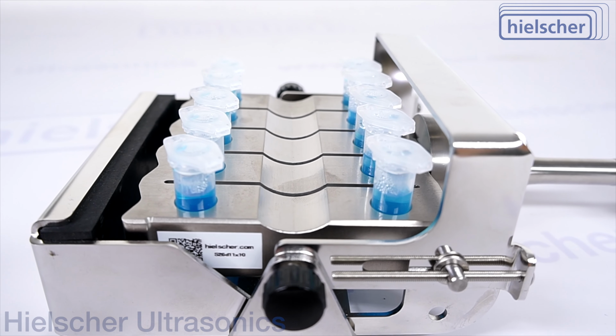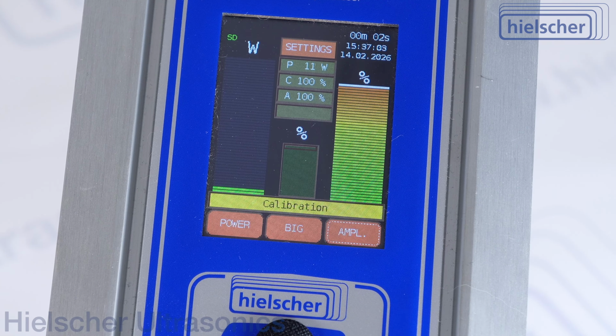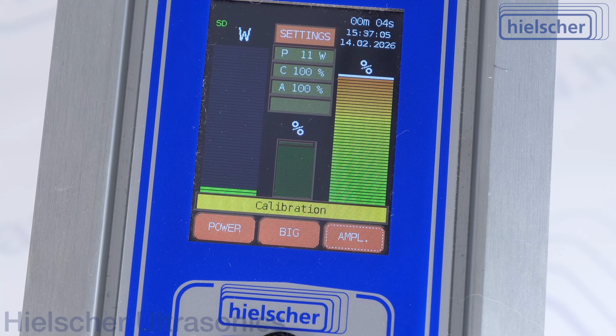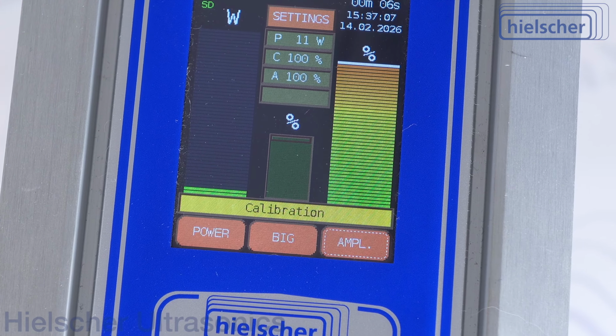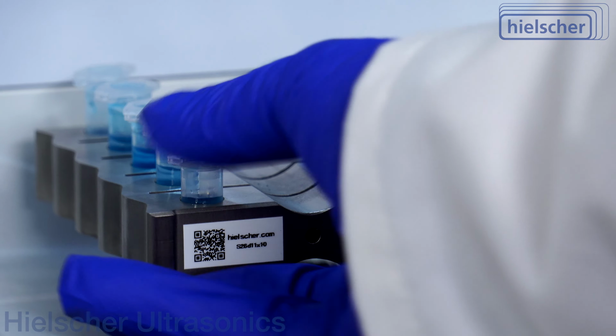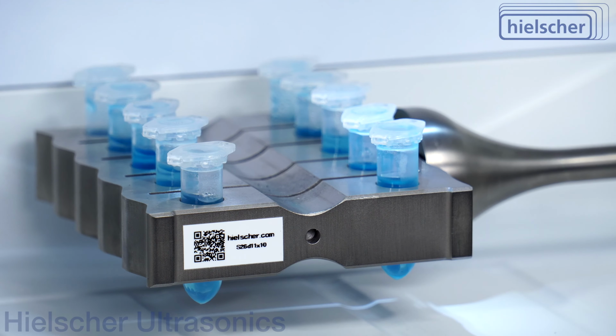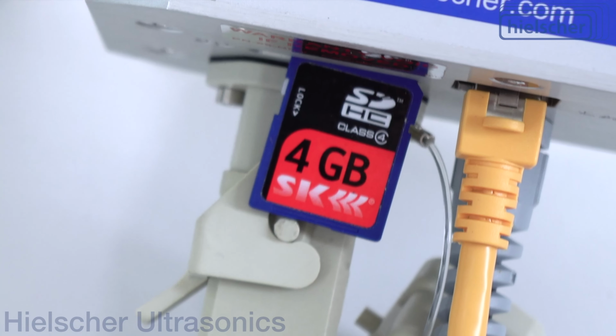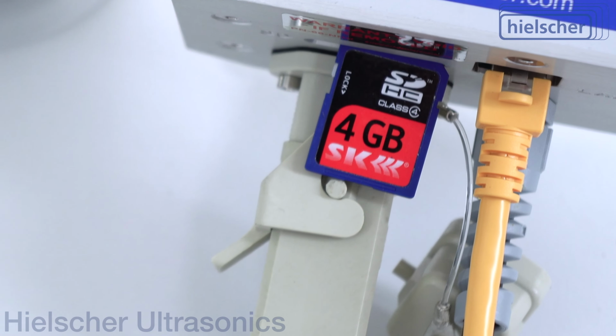During calibration, the system runs without any vials inserted. It measures the power needed to vibrate the VialTweeter alone. This value is used as a baseline. The device then calculates the net power delivered to your samples during sonication. Total power and net power are saved automatically on the SD card.